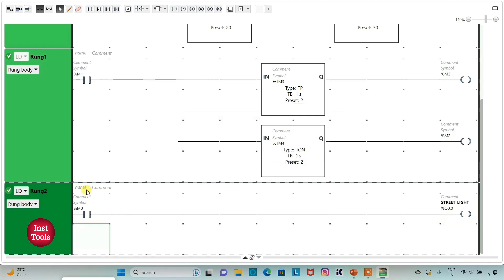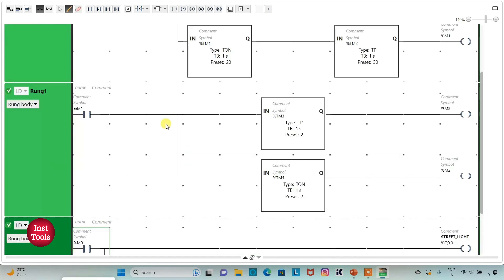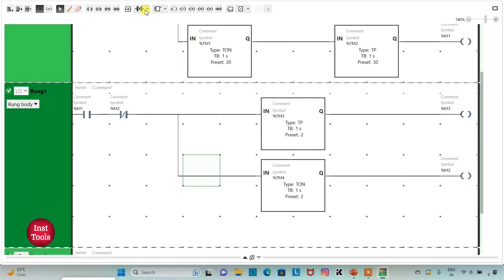Here I will insert one more normally open contact in parallel with M0 and assign address to it as M3, then connect it. Memory bit M2 will be used as a normally close contact here. I will insert a normally close contact and assign address as M2. Then I will insert one more normally close contact and assign address as Q0.0, which is the street light output.